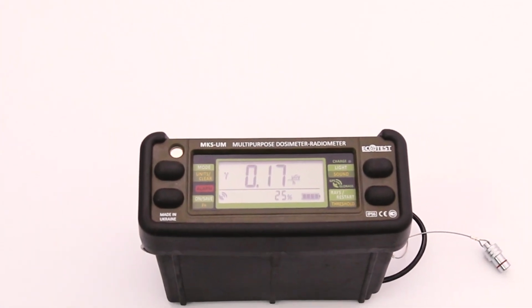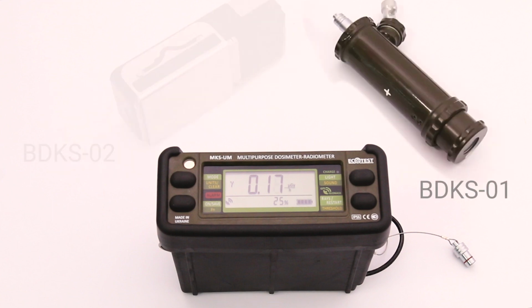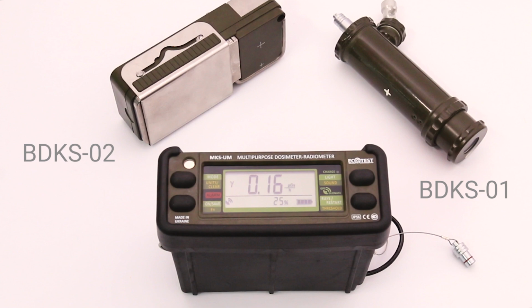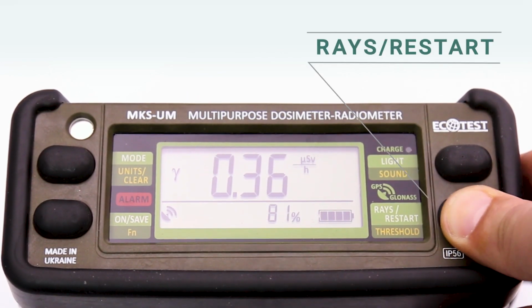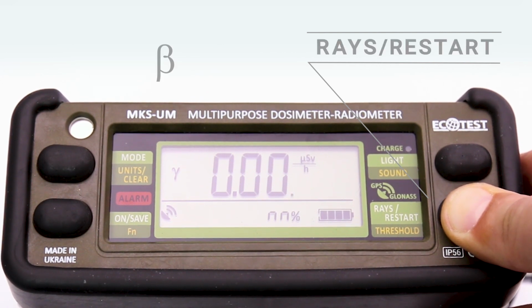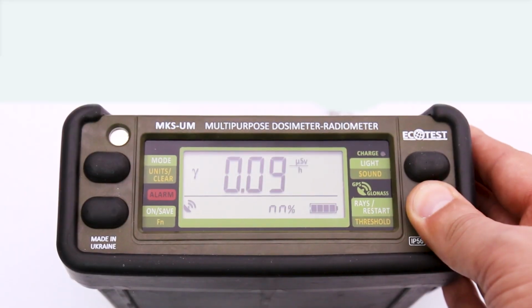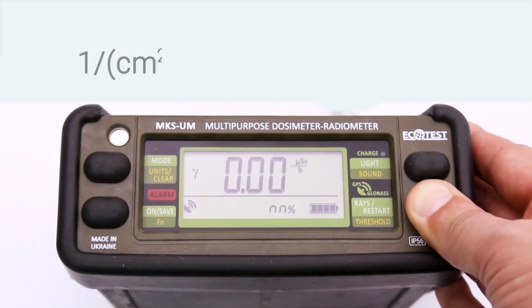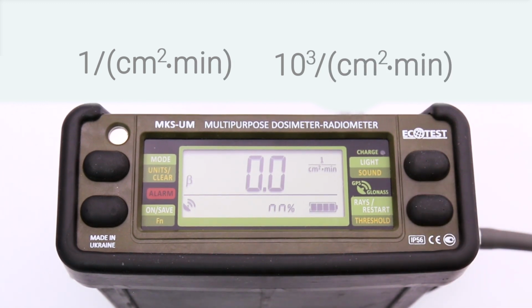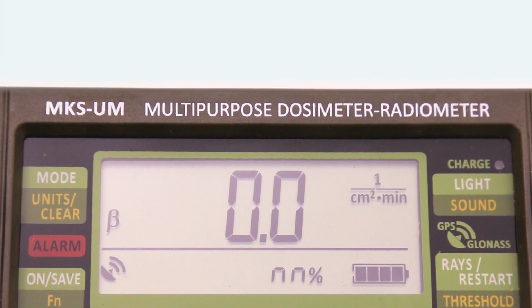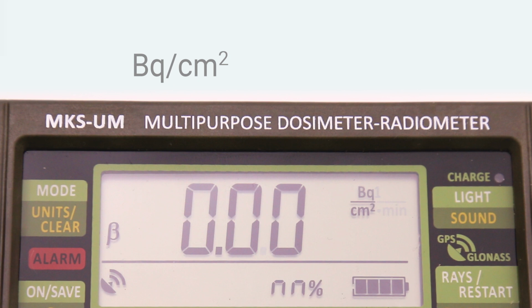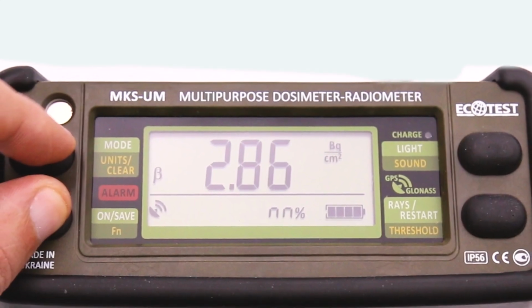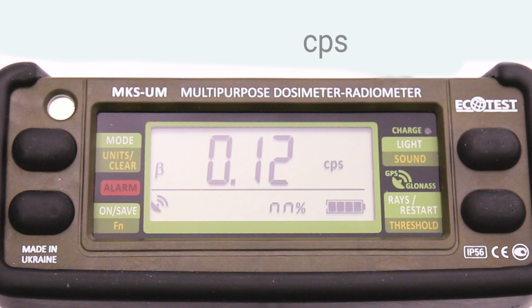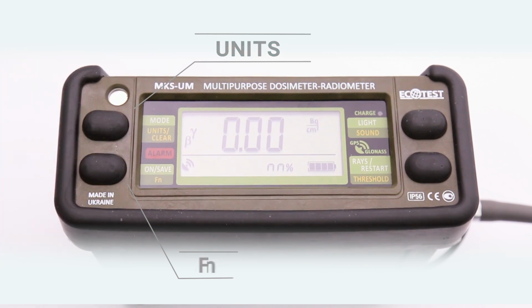The beta radiation parameters are measured by the BDKS-01 and BDKS-02 detecting probes. Press Rays Restart Long to select the beta radiation type. The surface beta particles flux density is displayed in particles per square centimeter per minute. The surface activity of the beta-emitting radionuclides is displayed in becquerels per square centimeter and kilobecquerels per square centimeter. The counting pulse speed of the beta radiation detector can also be displayed in counts per second. Press FN and units simultaneously to change the measurement units.